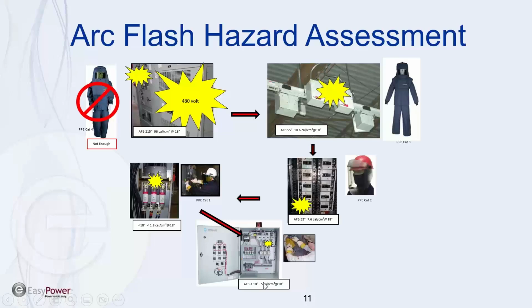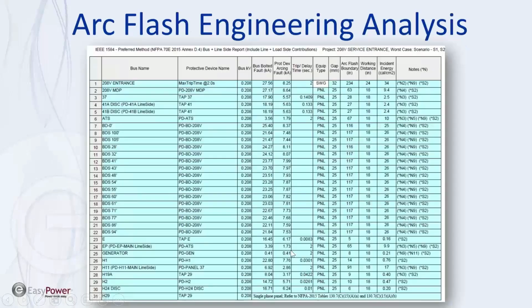So we got 0.5 calories, which is less than 1.2, so you don't need a shield, but that doesn't mean you don't want protection for your fingers, because at 2 inches away it could be 5 or 6 calories. That'll certainly burn your skin to a second-degree burn. So rubber gloves with leather protectors are both shock and arc flash protection.